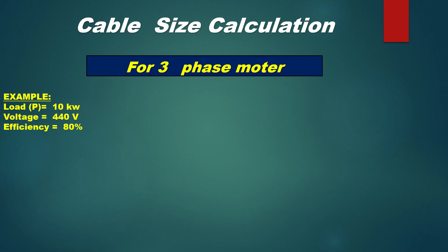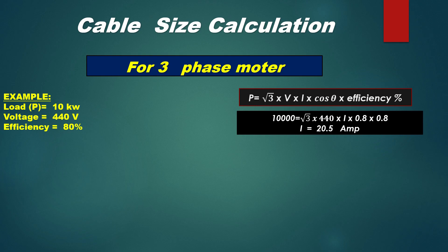Load P is equal to 10 kilowatt, voltage is equal to 440 volt, efficiency is equal to 80%. Now put the values in this formula. P is equal to under root 3 multiplied by voltage multiplied by current multiplied by cos phi multiplied by efficiency. Now put the values: 10,000 is equal to under root 3 multiplied by 440 multiplied by current multiplied by 0.8 multiplied by 0.8, so the answer is current is equal to 20.5 ampere.